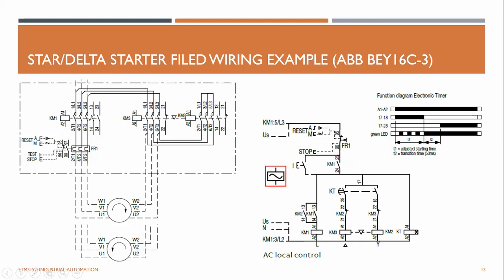And we have these three contacts, and the KM1. Someone has to press this one, right? This is the start button, and this is the stop button. If the stop button is pressed, the power to the downstream will be disconnected. When someone presses start, the current will flow from here and go to A1, A2 of the timer coil, right? KT is the timer coil.